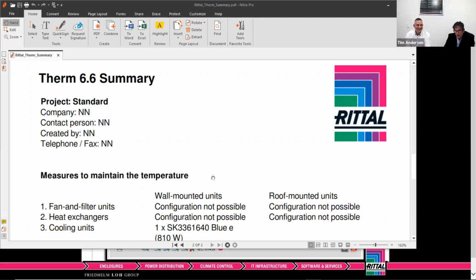Oh, I can answer that. Of course, the moisture content of the air - humidity is your first factor. Then based on your ambient temperature and humidity, you can work out the dew point, which is the temperature at which vapor in the air turns to liquid. We do that calculation, and Therm can do that too. So you work out the dew point, and if you keep your temperatures above it, you don't risk any condensation.